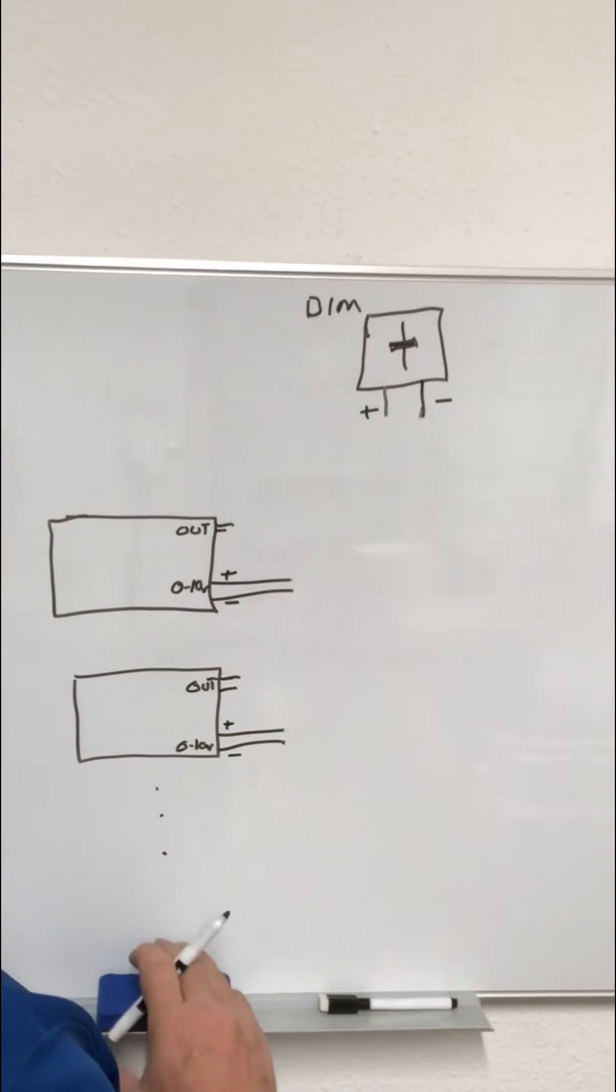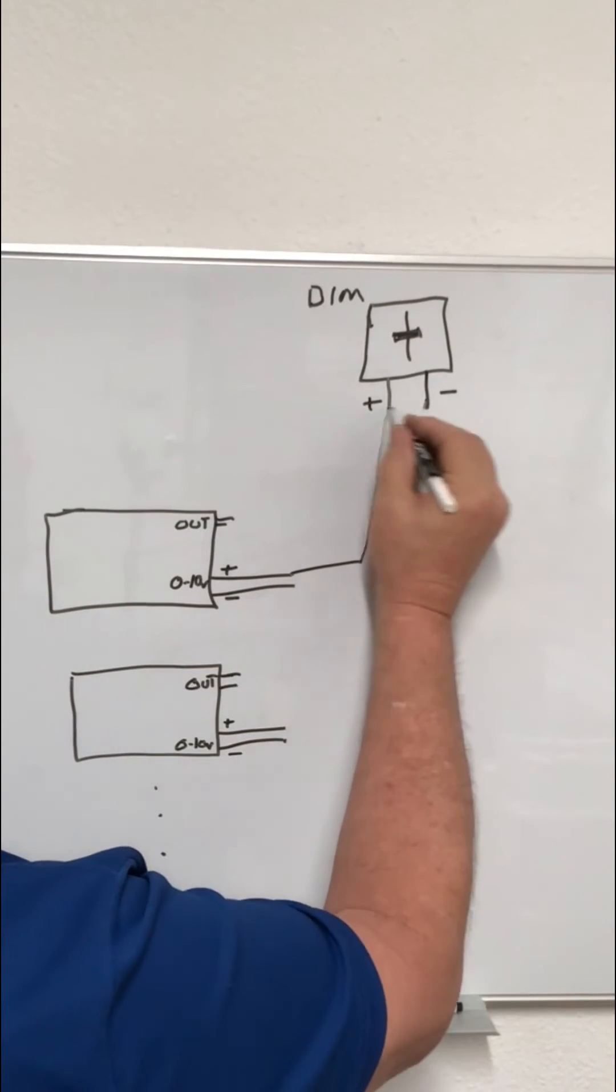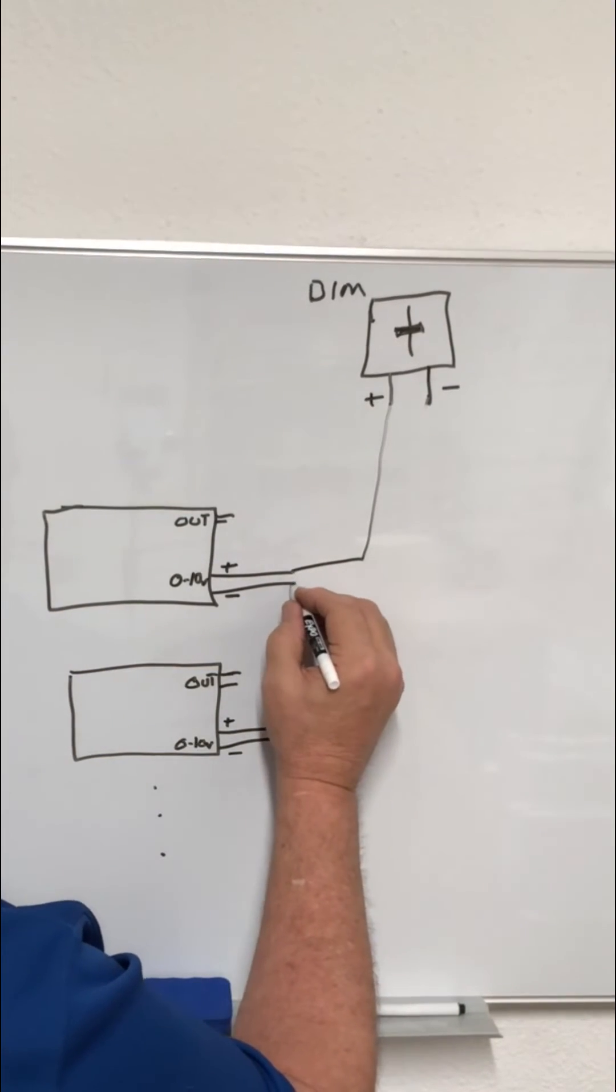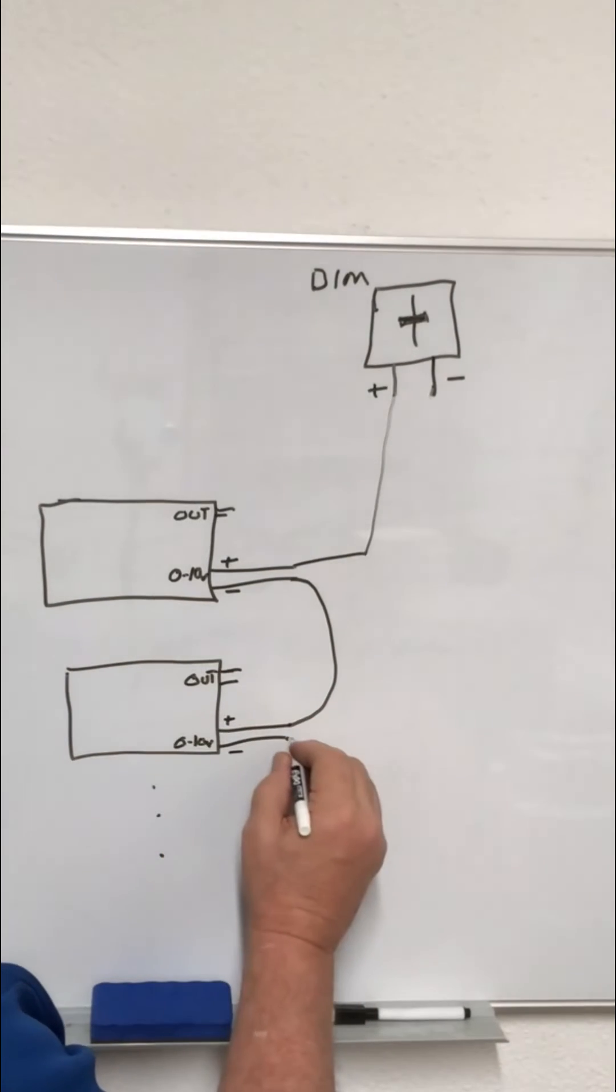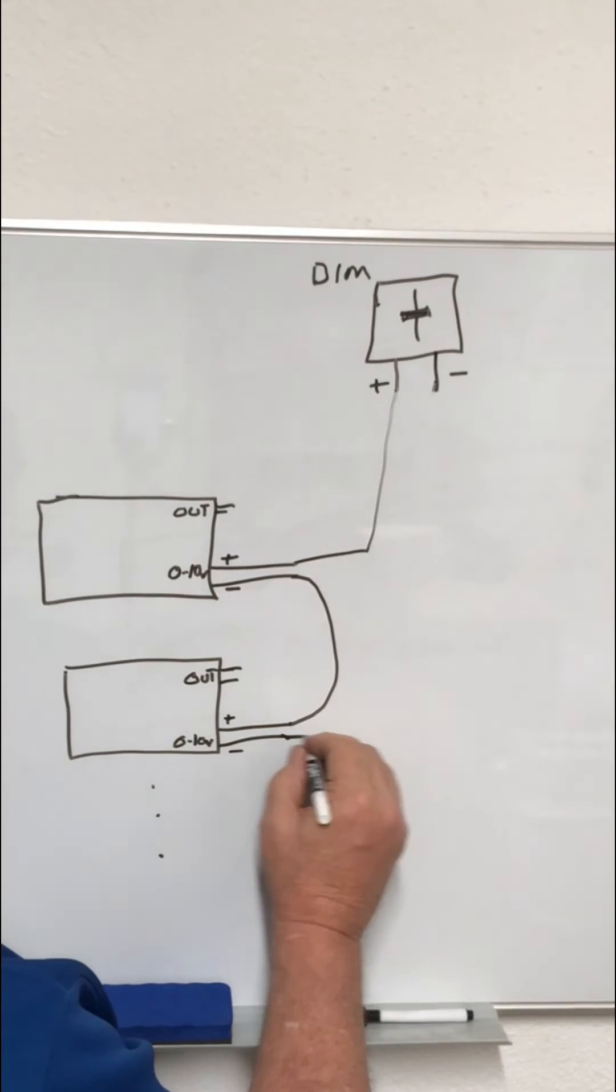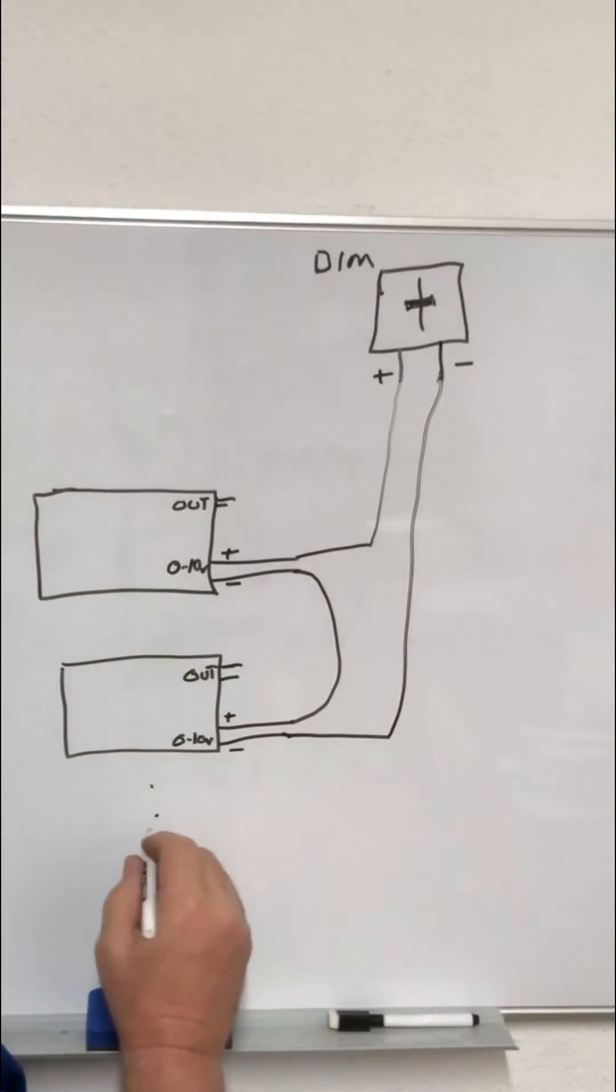...is where you'll have the positive to the dimming circuit and then the negative of one driver going to the positive of the next dimming circuit, and then the negative going back. This is considered daisy chain.